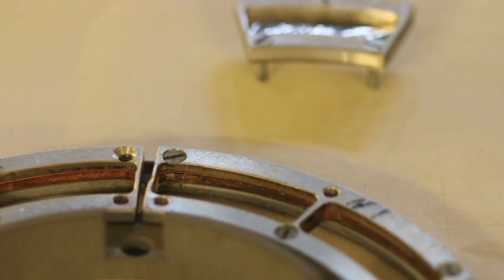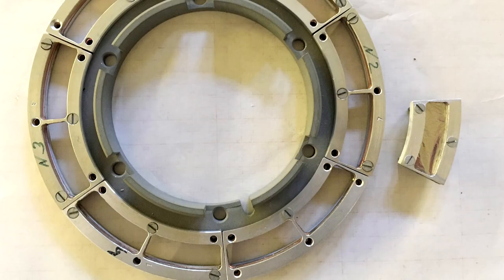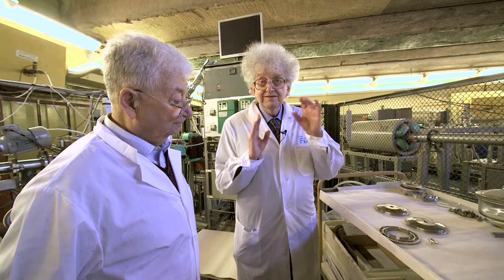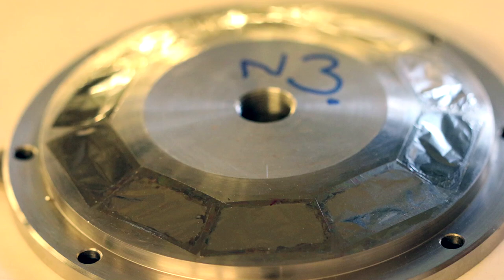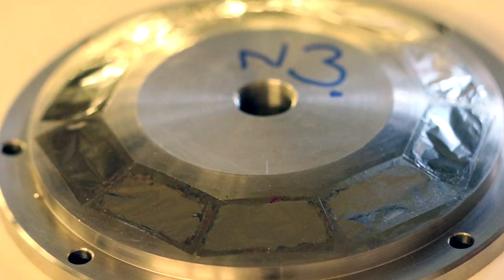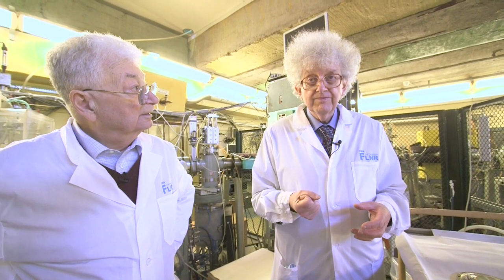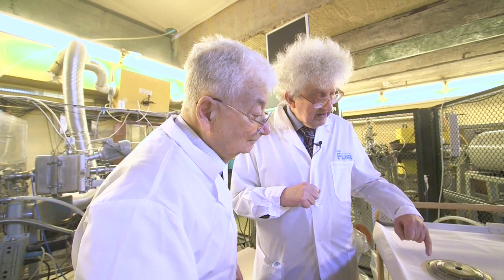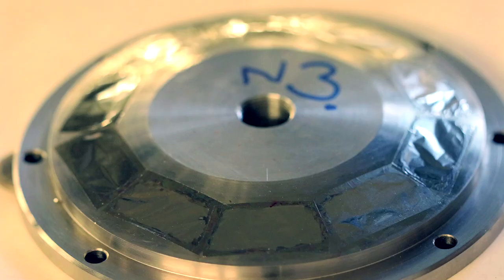The wheel is going round really fast, much faster than a CD, so that no particular spot on the target heats up too much from the energy of the beam. This titanium window separates the high vacuum of the cyclotron from the hydrogen atmosphere around the target itself. You can see that the beam really eats into the window — it goes this bright purple colour — but a new set of windows is clean and silver.